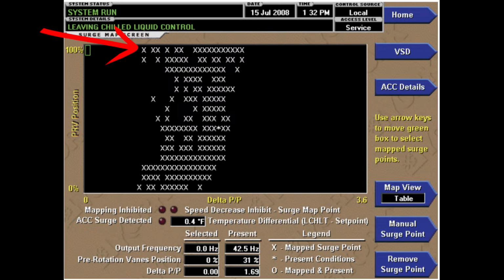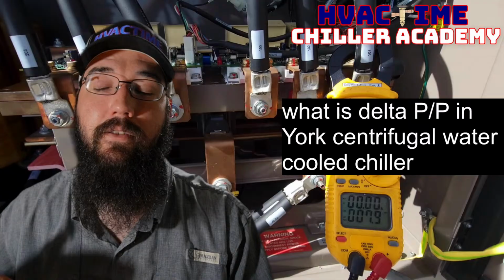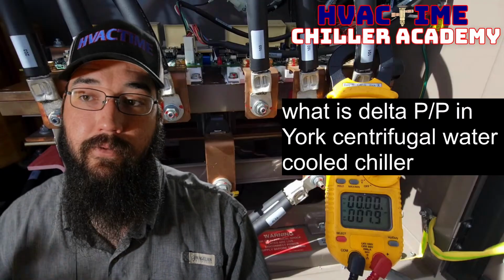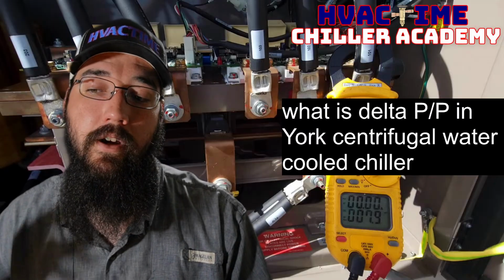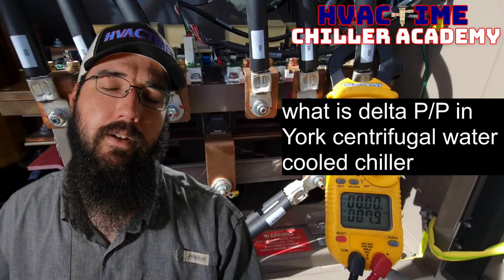And that is because we're trying to not go into a surge condition, which means we have to maintain a minimum speed. Because if the compressor was allowed to slow down, then the surge map is telling the machine that, well, if you slow down at all, I'm going to go straight into a surge, even though the problem that was causing the surging has already been resolved. So just something to be mindful of. That is a condition where you really do just have to clear the map and allow it to remap itself. That means that the chiller is going to push itself into some surging for a couple of days or so, off and on, until it remaps the actual points that should be there.